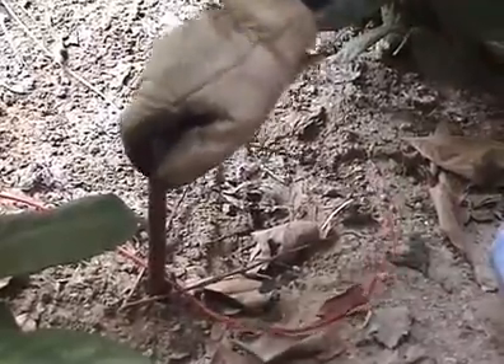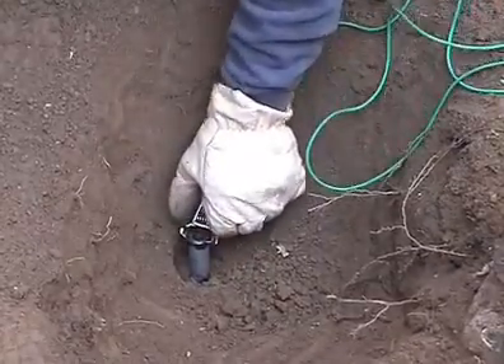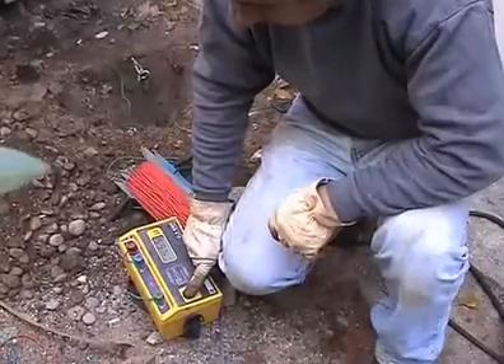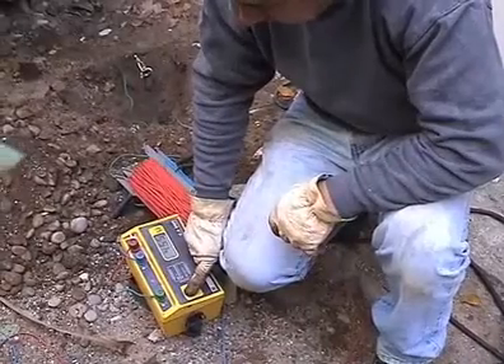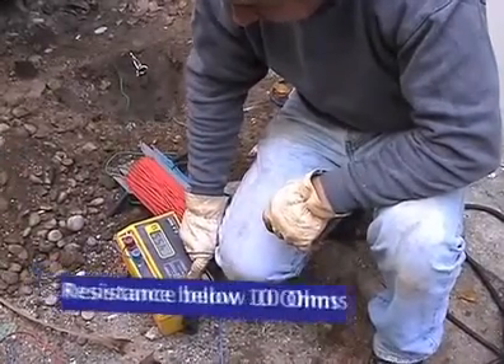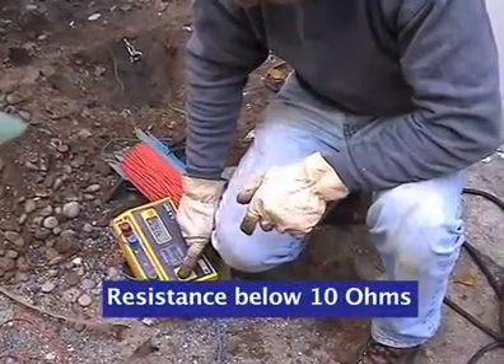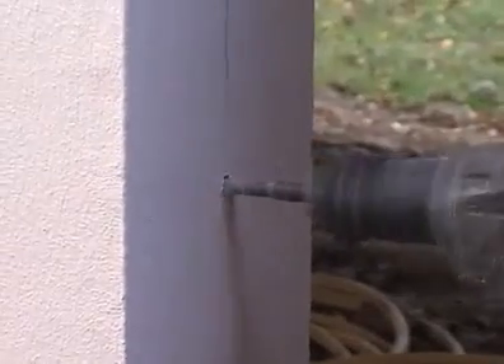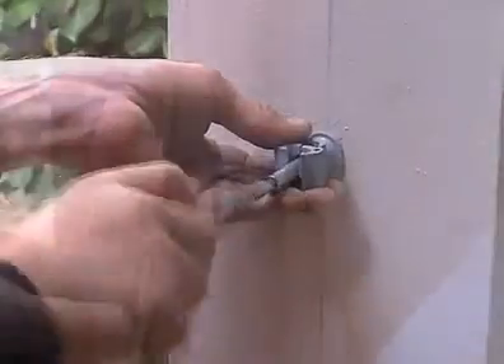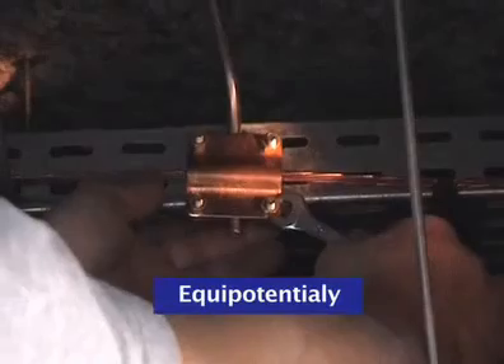Ohm values lower than 10 ohms in accordance with early streamer standard NFC 17102 are recommended. A fundamental part of the installation now takes place by connecting the electrical earthing system of the building and the lightning earth system in order to achieve a good equipotential bonding between these 2 earthing systems.